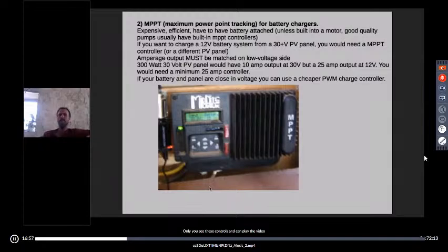That is an option. Most modern expensive pumps, like if you go to Grundfos or Lorentz or Sun Pumps and get a good quality submersible DC pump for your well, it has a built-in MPPT controller. That controller basically takes the DC electricity coming down the wire and sets it to a voltage that's ideal for the motor. So expensive, good equipment already has this stuff built in.